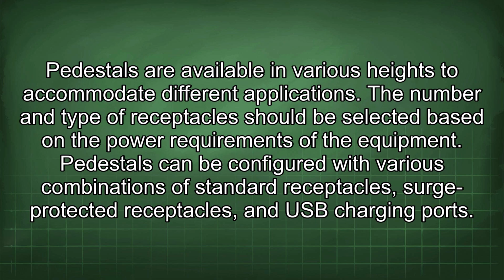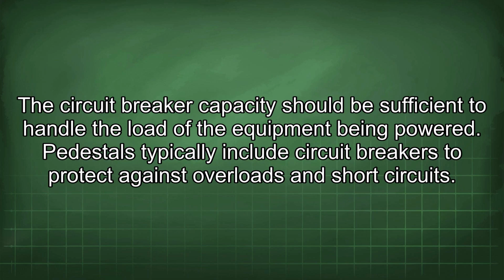The number and type of receptacle should be selected based on the power requirements of the equipment. Pedestals can be configured with various combinations of standard receptacles, surge-protected receptacles, and USB charging ports. The circuit breaker capacity should be sufficient to handle the load of the equipment being powered. Pedestals typically include circuit breakers to protect against overloads and short circuits.